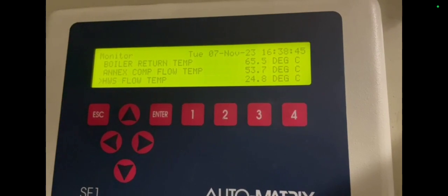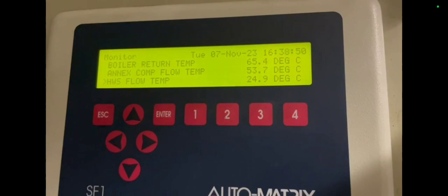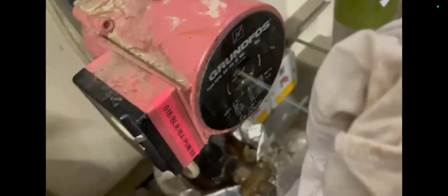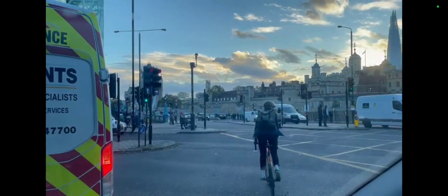There's a three-way valve there, and then in between I saw a bypass on the three-way valve — this is the flow going into the calorifier and the flow going out. This pipe wasn't getting hot going into the calorifier. You can see the flow temperature has gone up from 22°C to 24°C — when I arrived it was 22, now it's going up. The pump was spraying water all the way across the room when I took it off.